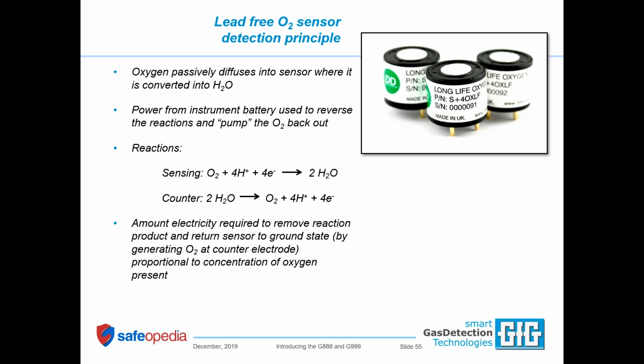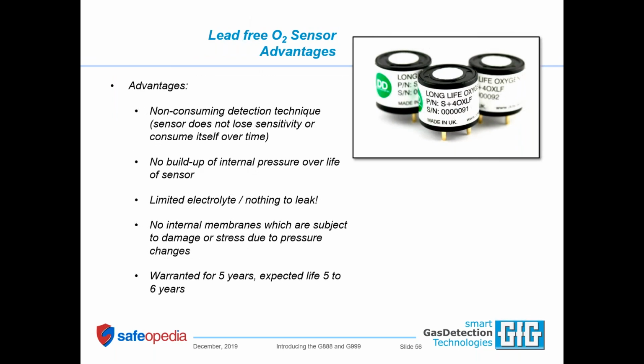In the case of the lead-free sensor, oxygen diffuses in, it's converted by a reaction into water, and the instrument applies power to the sensor to cook out or pump out the water in the form of oxygen. So oxygen in, oxygen out. The only thing that gets consumed is a little bit of power. So even though we warrant the sensor for 5 years, the instrument warranty, just like our other products, is lifetime on the non-consuming components. In the case of the oxygen sensor, the standard warranty is 5 years. We expect it to last even longer, at least 6 years. But the advantages of the lead-free sensor: you don't have a buildup of internal pressure over the life of the sensor as the lead electrode is consumed. It does not have a bunch of electrolyte that tends to leak.